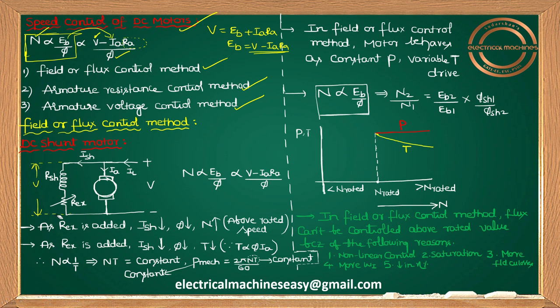The method name itself is field or flux control — meaning we are changing the flux of the DC shunt motor by connecting a variable resistance Rx. Since I connected a variable resistance, I vary the Rx value, so the shunt field current Ish varies, and therefore flux also varies. So please don't take flux as constant in the field or flux control method.